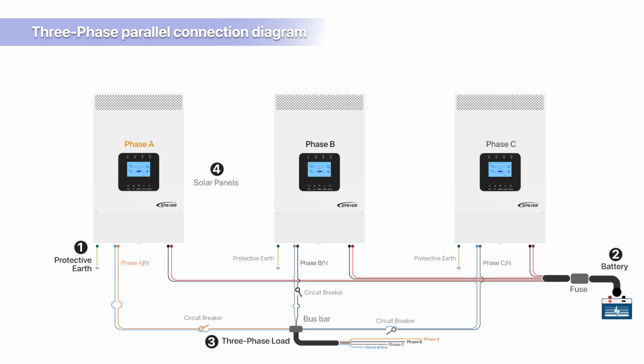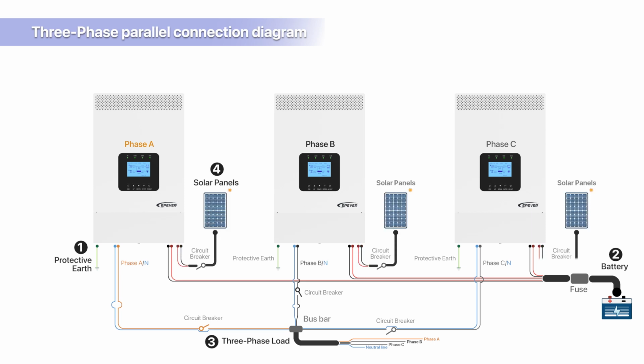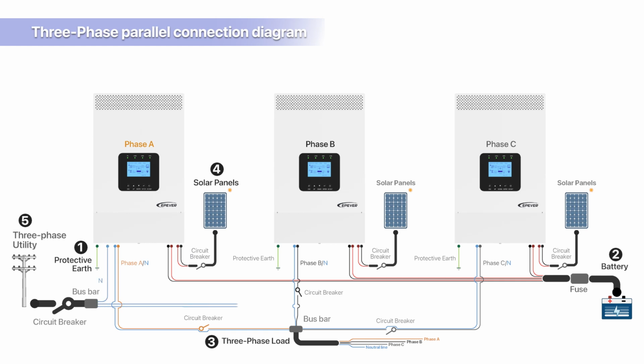Solar panel connection. Each device should be individually connected to solar panels. The total output power, wire gauge, and length of the solar panels for each device should be equal. Three-phase grid power connection. Connect three-phase grid power to each device, observing the following. Connect the grid power's neutral wire to the bus bar first. Then, from the bus bar, connect it independently to the grid power input side of each device.